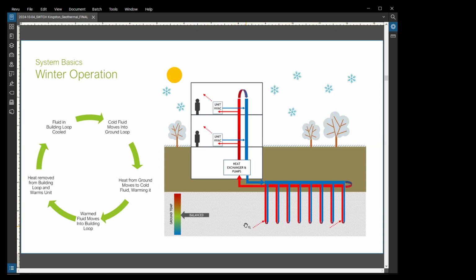Okay, great. You can see the cursor. So basic winter operation is, like we said, the ground temperature throughout the year when you get to depths of 800 feet is fairly consistent. It's not freezing, it's not crazy hot. It equilibrates to a constant temperature. So what's happening in the winter time is that the fluid that is going down into the loop through the inlet is colder than that ground temperature. And by the time the fluid travels all the way down the loop and then back up, and then because it's all a continuous loop, it goes down the next one and then back up, and it keeps going down and up and down and up until it gets back to the building, it basically pulls heat from that ground and raises the overall temperature of the loop, so that when it goes back into the building, that temperature is now warmer.